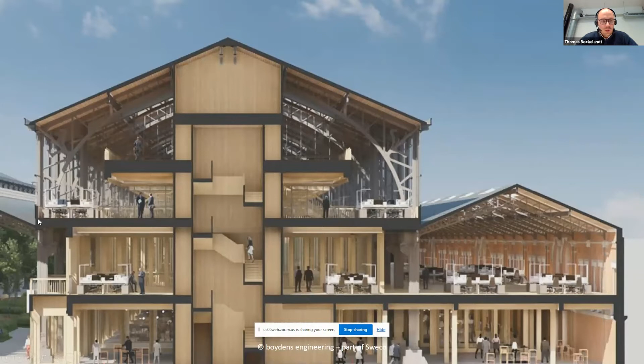Now for the technical part: what did we do for climatization? As we wanted to use the heat pump as the only provider of heat and cold, we went for climatized ceilings as much as we could, putting them in all new floor slabs. On top, from a heritage point of view, it was not reasonably doable to put climatized ceilings, so there we chose fan-powered convectors on the side, shown here in white. The ducts are all in the raised floor.